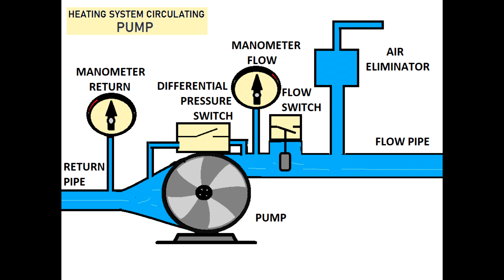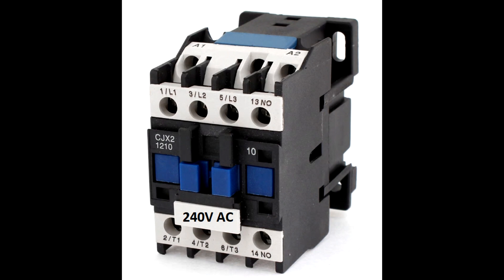Please stop the video and have a look, because every single label will help you understand what I am talking about. Some commercial boilers have a differential pressure switch and flow switch, and believe me, some do not — and I will explain to you why. This is a contactor, and the contactor is used to run the pumps in a commercial installation.